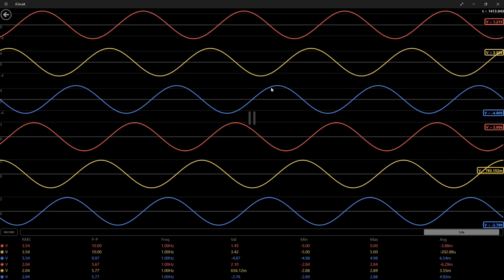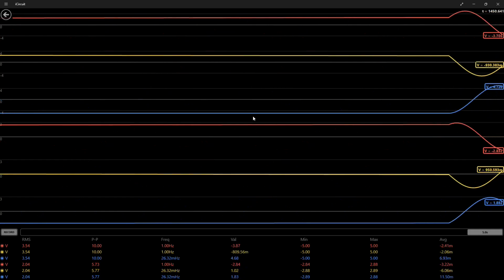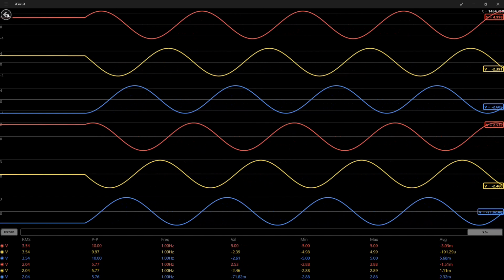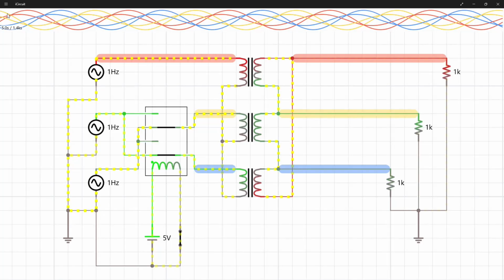What is our phase rotation? Well, now it's C comes first, then B, then A. Bottom is the same. C, and then B, and then A. Or you could say it's A, C, B, if you're looking at which peak comes first, doesn't really matter. It's still CBA now. So our phase rotation has indeed gone to CBA, and the primary is lagging the secondary by 30 degrees.